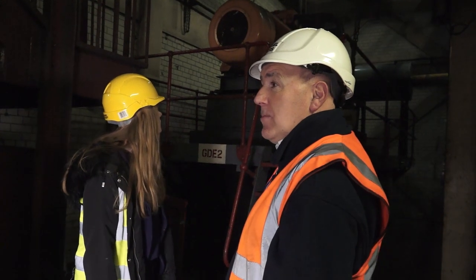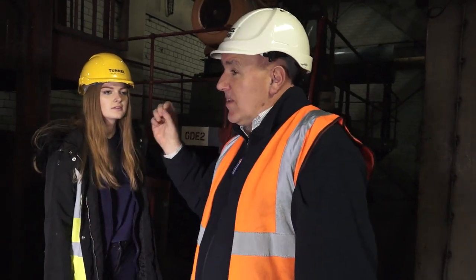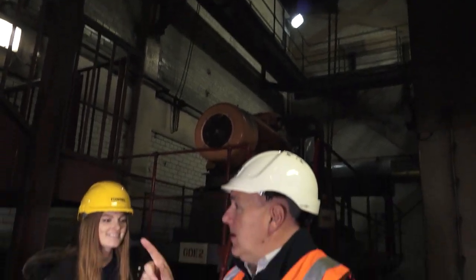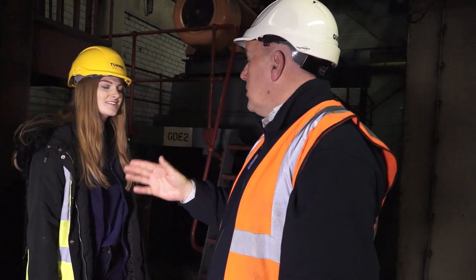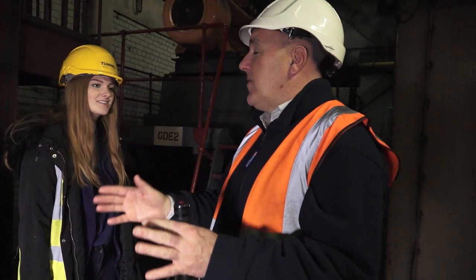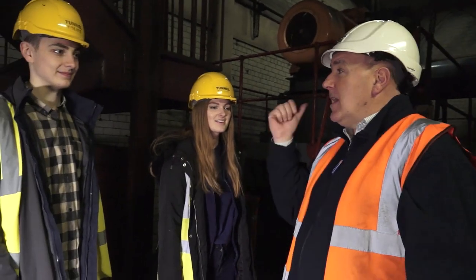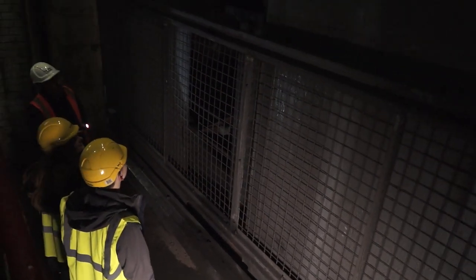You may be wondering why that fan is not on at the moment. These fans are only really on when we've got stationary traffic in the tunnel — the fresh air fans do it for us otherwise. The size of the fans: they're 28 foot in diameter, they weigh 25 tons, and they have the capability to pull or push half a million cubic feet of air in one minute — to simplify that, six Olympic-sized swimming pools in one minute. When we get the fan on we'll just have it on half speed; at full speed it can do roughly about 70 revs per minute.